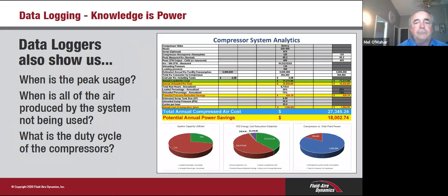And then if we do a data logging, we'll generally do up a full report on it. It'll tell you what the horsepower of your machinery is, the models, the efficiency of it, the output. And depending upon the types of controls you have, whether it's modulation or online, offline, we can calculate an energy savings cost for that. And when you take a look at some of these, you'll see that we have several customers where it'll have a 1 or 2 year payback on it, if they're going from, let's say, a modulation system to a variable speed.